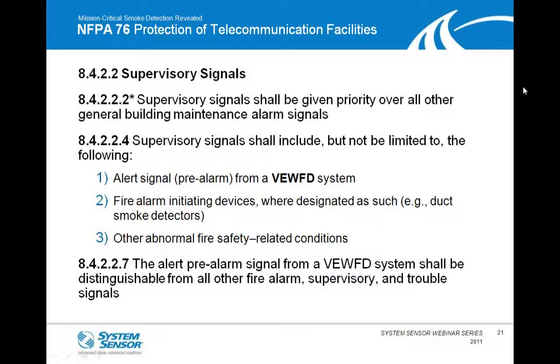Excuse me, the supervisory signals shall include, and are not limited to, and this is a truncated list, not the complete list that shows up in NFPA 76. But again, a supervisory signal would be viewed as that alert or pre-alarm signal, especially with a very early warning fire detection system.